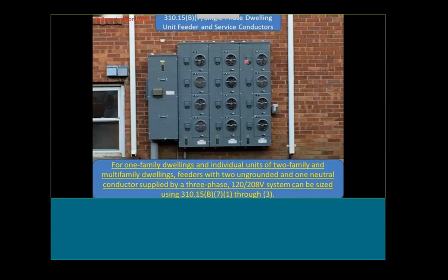The problem was, this has always been limited to 120/240 volt single-phase systems. So you could use it for a house, a duplex, or multifamily townhouses and apartments, depending on the setup. But if you're talking about a big apartment complex, you're probably doing a three-phase 120/208 volt service, and if that was the case, you couldn't use the smaller conductor sizes. They changed that in 2017—I was absolutely floored, and I'm glad. I think it's great. This rule now applies to 120/208 as well as 120/240.